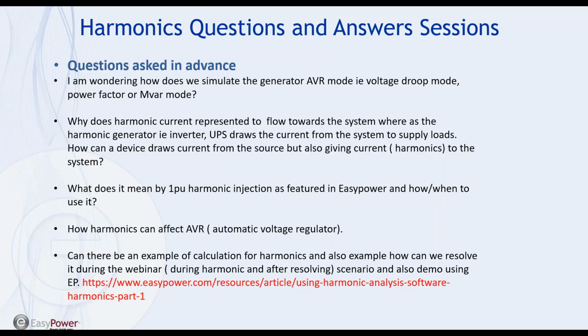What I can say though is in the real world, we have seen one project where we had a tap changer. It's not quite a voltage regulator in terms of a generator, but we had a tap changer that did have a lot of issues related to a high frequency voltage distortion within the facility, and the way we corrected that was through a high pass harmonic filter. So we did see some sporadic operation of a tap changer that was regulating voltage, and it was having issues because of distortion. So it can impact it. If this is an equipment issue, I would suggest that you contact the company building the voltage regulator.